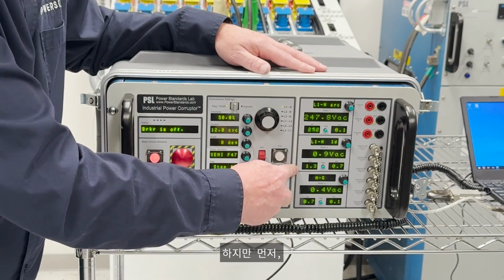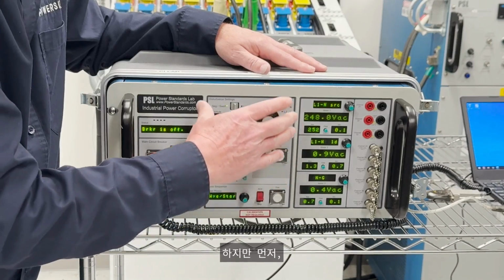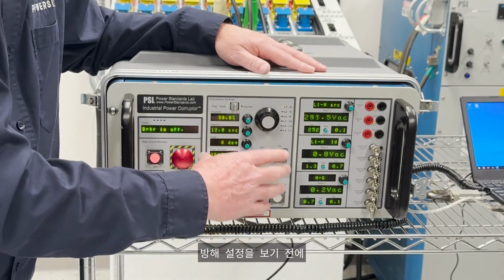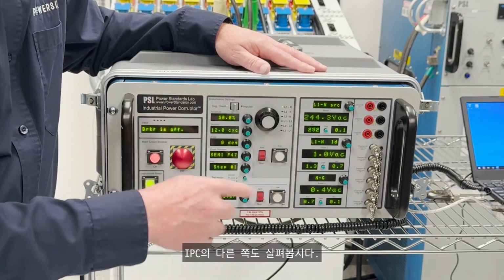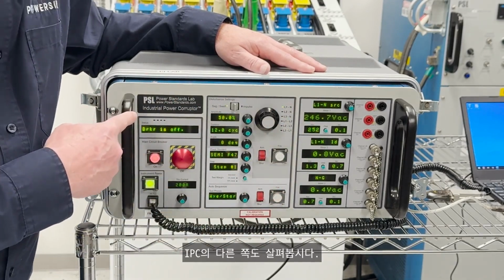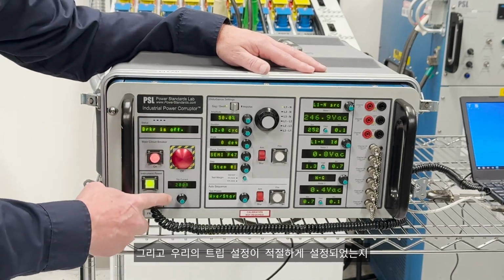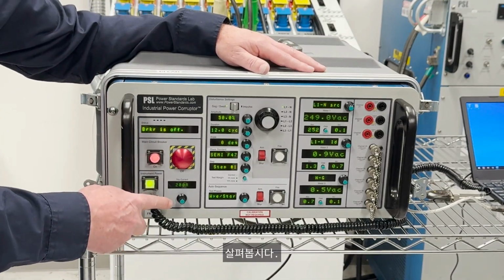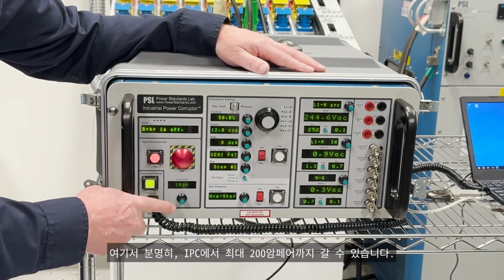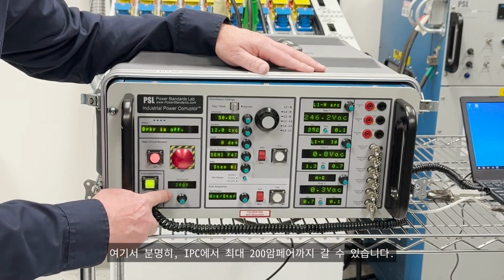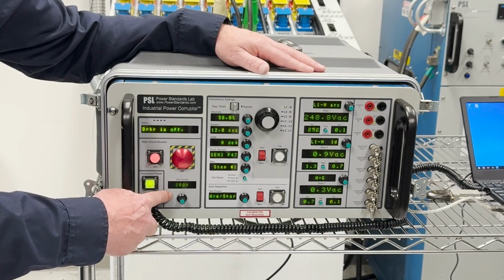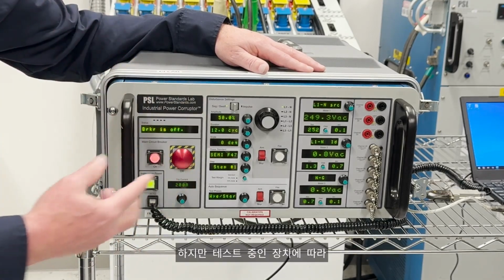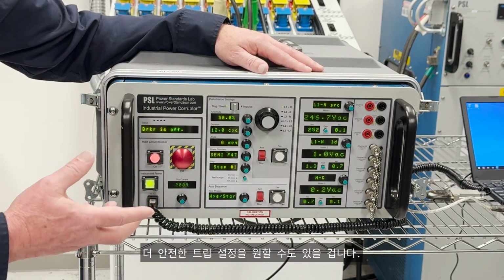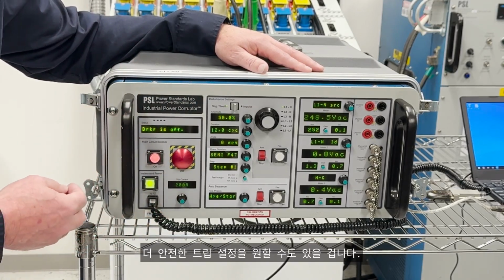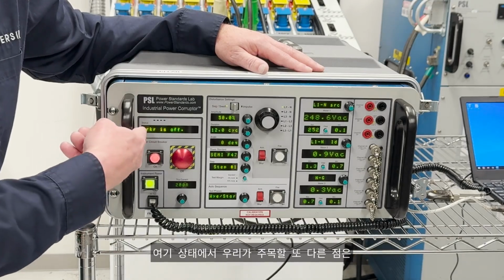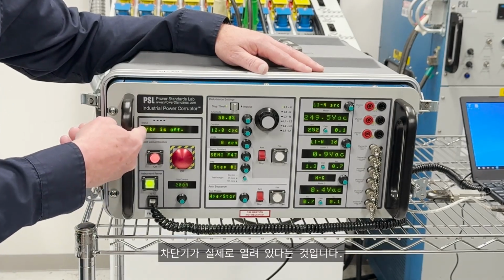But first, before we look at any of the disturbance settings, let's also look at the other side of the IPC and see if we have, first of all, our trip setting set appropriately. Clearly, here we can go up to 200 amps on the IPC, but you may want to have a trip setting that's lower than that, that's more secure than that, based on the unit under test. The other thing that we note here on the status is that the breaker is indeed open.